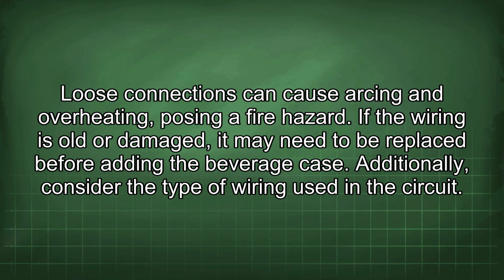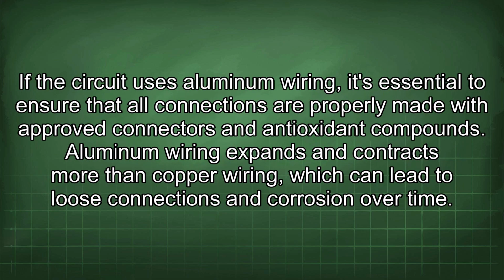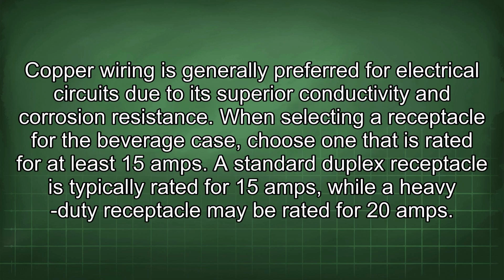Additionally, consider the type of wiring used in the circuit. If the circuit uses aluminum wiring, it's essential to ensure that all connections are properly made with approved connectors and antioxidant compounds. Aluminum wiring expands and contracts more than copper wiring, which can lead to loose connections and corrosion over time. Copper wiring is generally preferred for electrical circuits due to its superior conductivity and corrosion resistance.